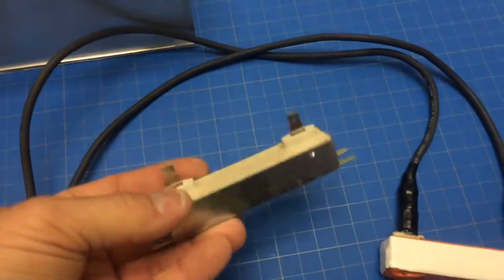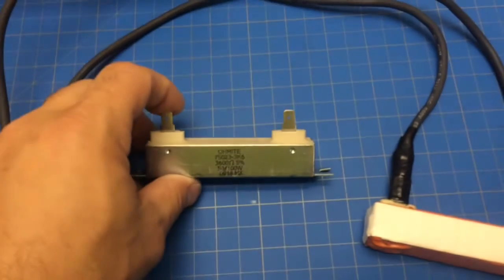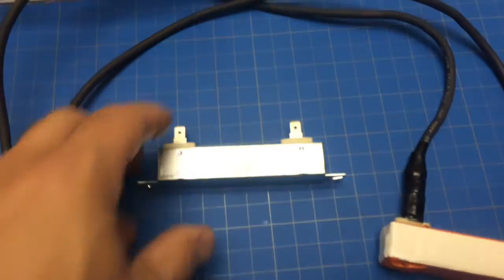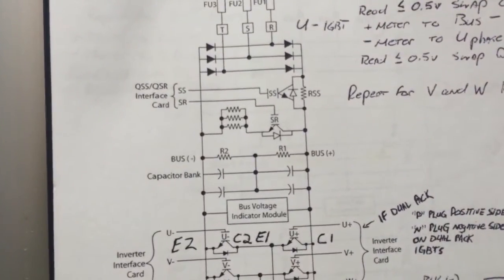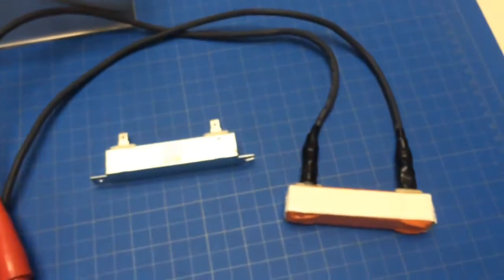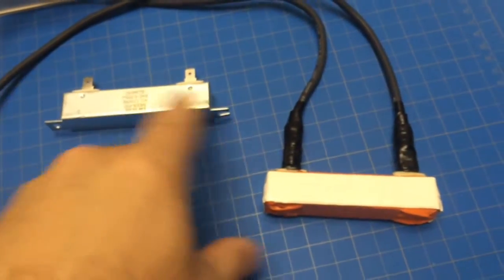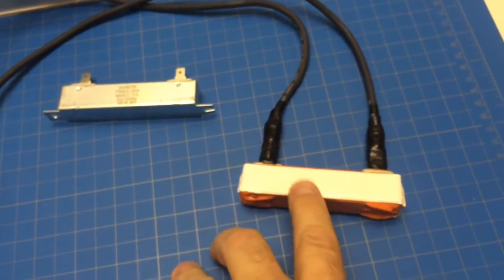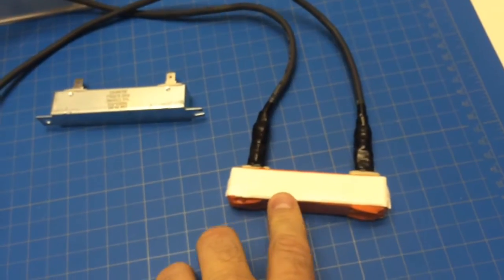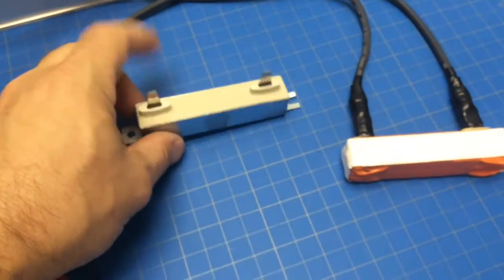This is the type of resistor that you see right here. This is a 50 ohm. This here is 3600 ohm though. The reason for the difference is it's actually a bleeder and a balance resistor for a large capacitor bank. Same style, both high wattage, mountable on a heat sink. These have been confused before, and someone has accidentally put a 50 ohm in there, but it just burns open pretty quick, so you couldn't accidentally forget about that.